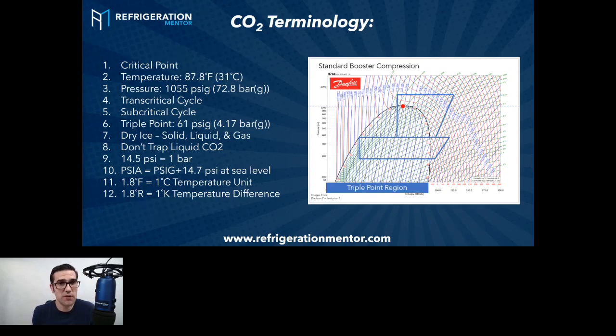We've been talking about for years, when you're charging 410A or any refrigerant, we really want to charge with liquid. Any blended refrigerant, you wanted to charge with liquid always. But now, when we get into CO2 and you charge a system, you need to charge with vapor first. So you've got to get above that triple point. These are some uniquenesses about CO2 versus the refrigerants you're working on today. You just need to know a few of these things that really help boost your knowledge, because a lot of the smaller systems are already charged.